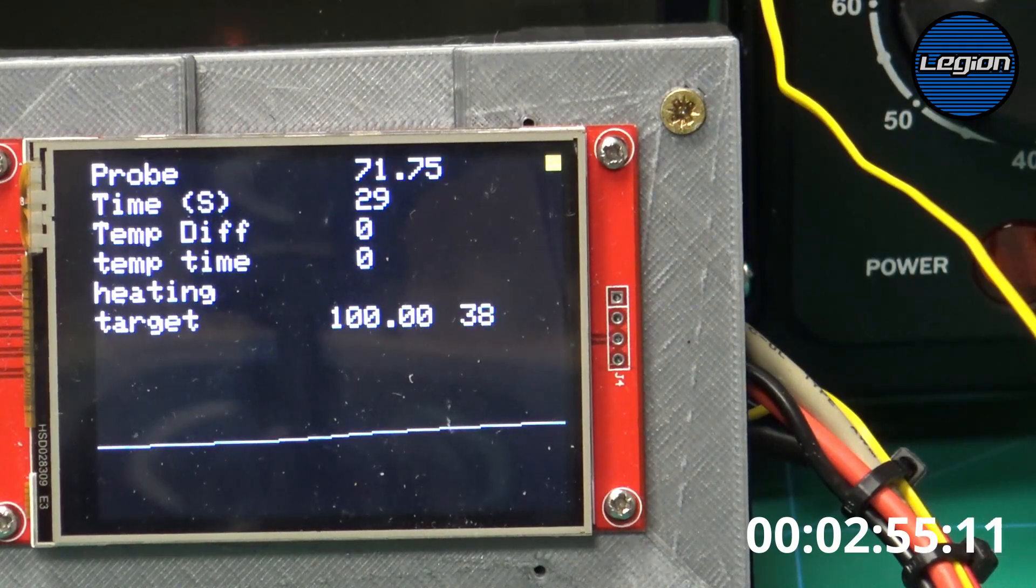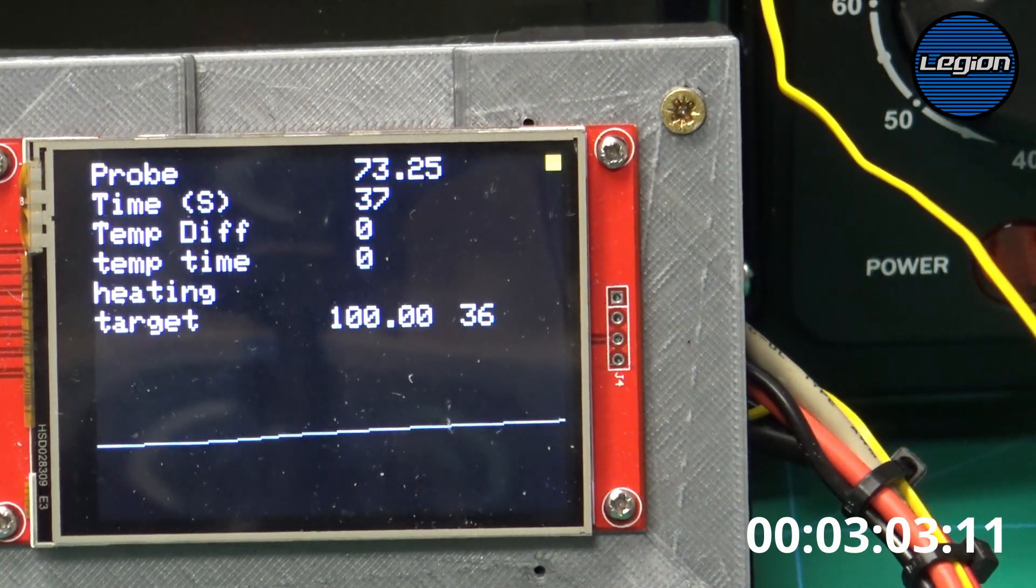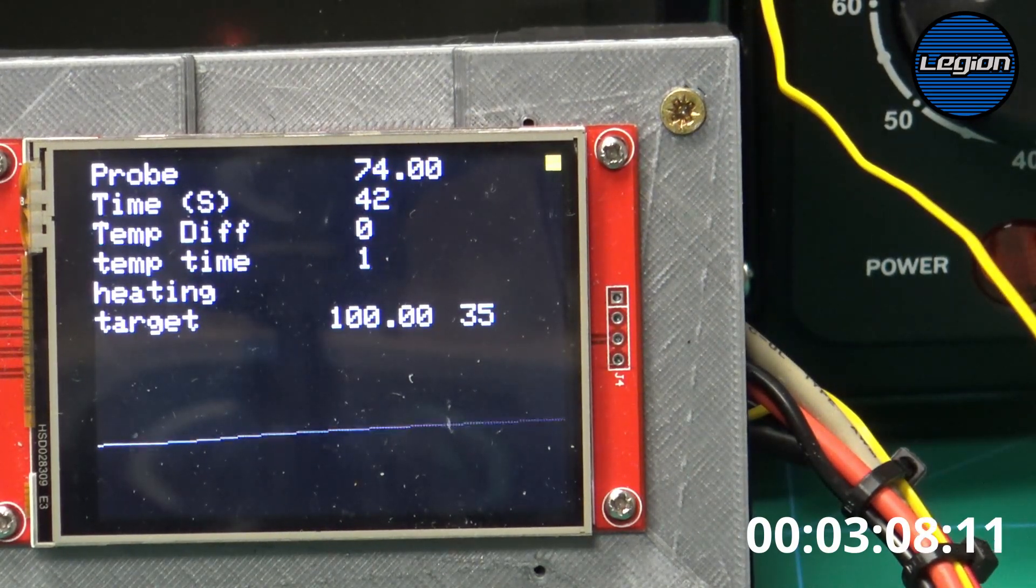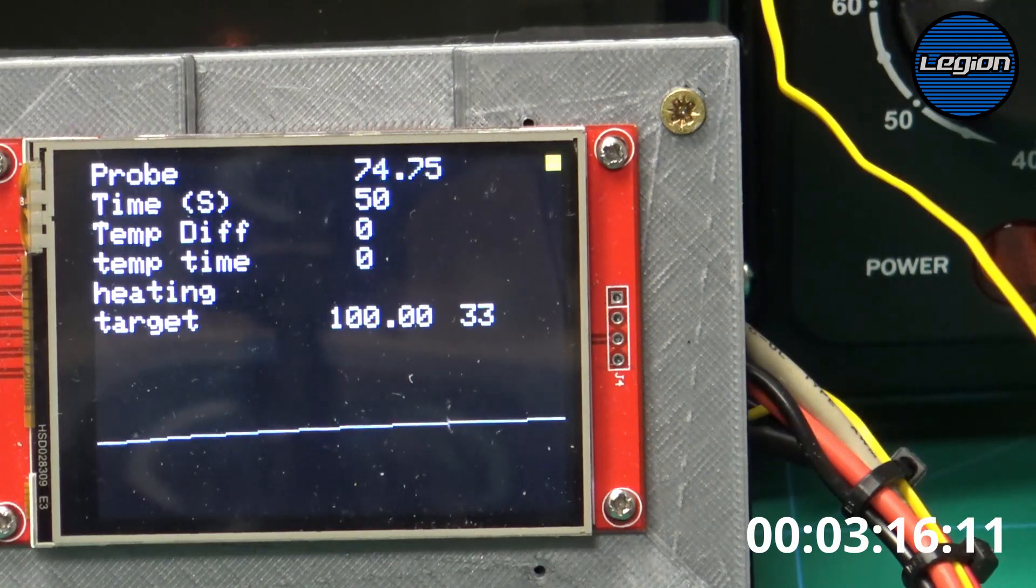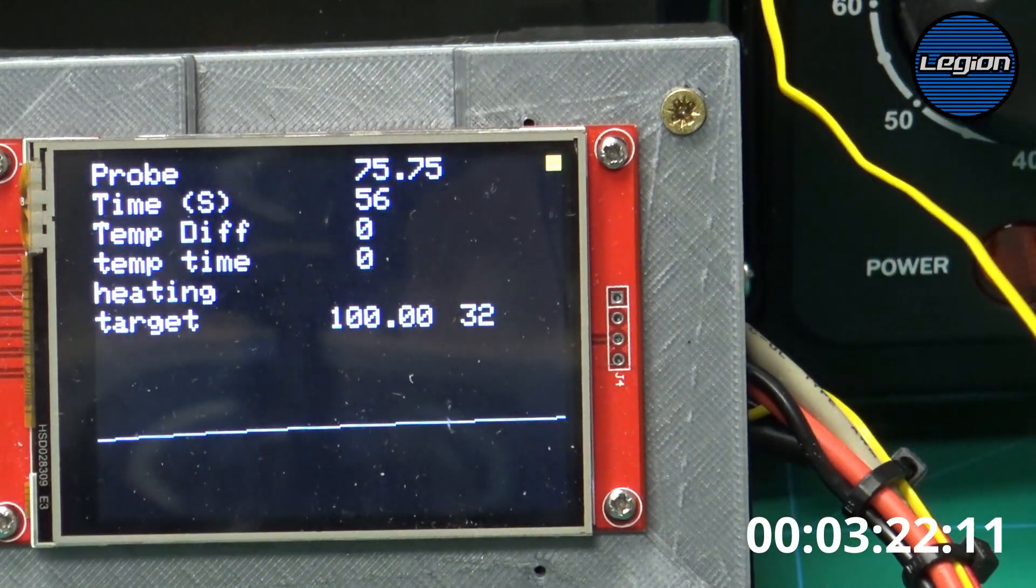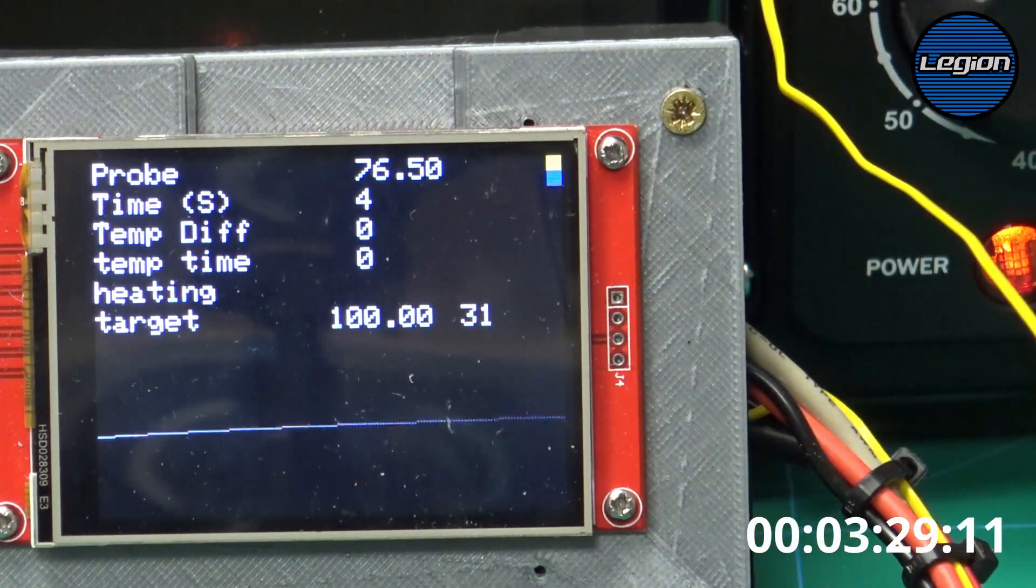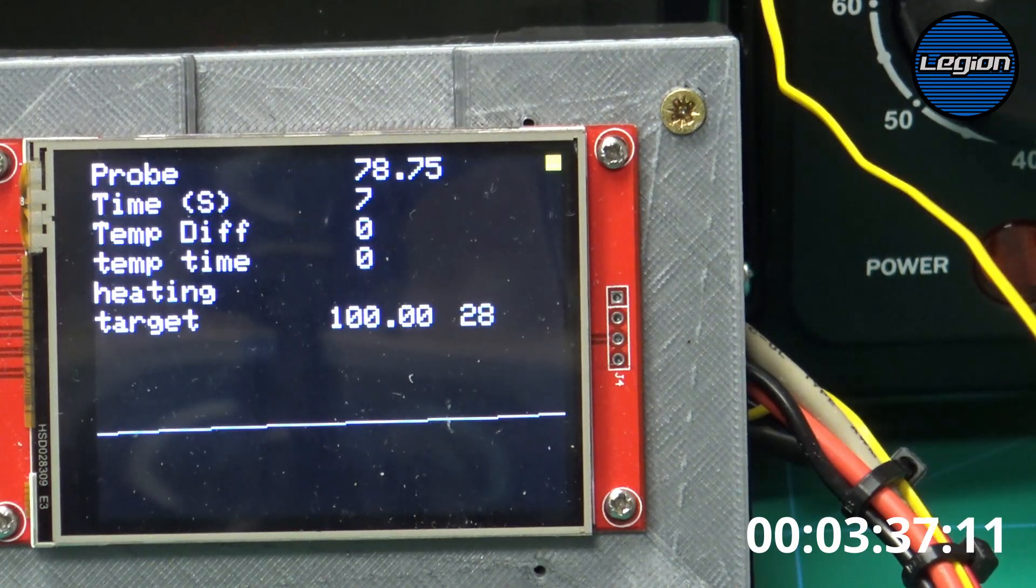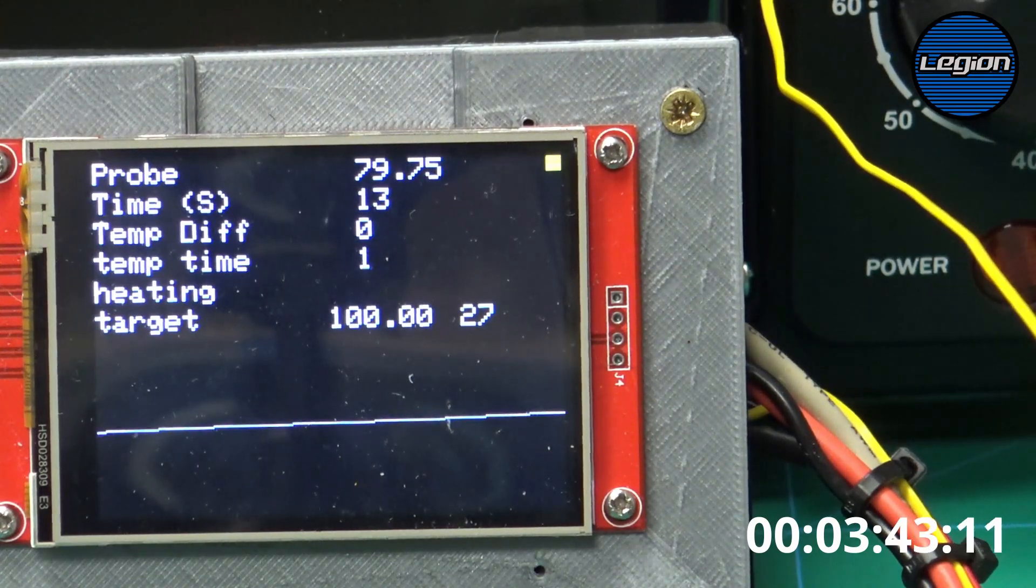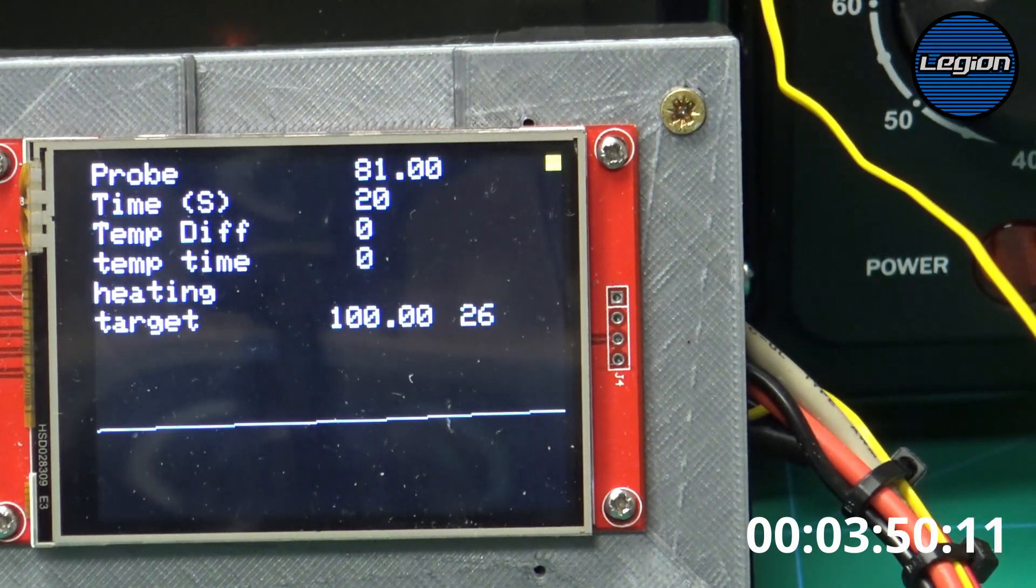So I've set up several zones and I can have as many zones as I like. The zones can be programmed to turn on for as long as we want and then wait for the temperature to stabilize for as short or as long as we want so that we could have a slow boost or an aggressive boost. So now that we're in the higher temperature range we need to see 3 seconds. So there we go 3 seconds and the element is turned on. So we're having a gradually longer time to wait for it to stabilize before we heat again.